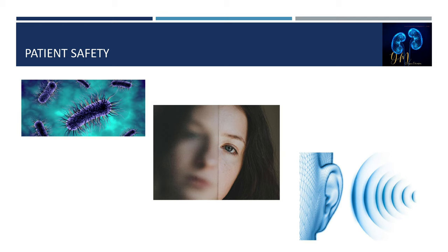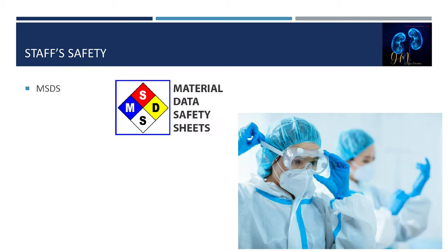Dialyzer reuse is safe if done correctly; done incorrectly, it can cause patient harm or death. Exposure to bacteria or endotoxin is a major risk. The patient's temperature must be checked and recorded pre-treatment and post-treatment to determine baselines and facilitate assessment for reactions. Introduction of germicide into the patient's blood may cause burning in the extremities, burning in the lips, vision or hearing loss, and even death. All patients are monitored for inadequate dialysis with kinetic modeling at least monthly. Matching the patient and dialyzer must be verified and documented every treatment by two persons.